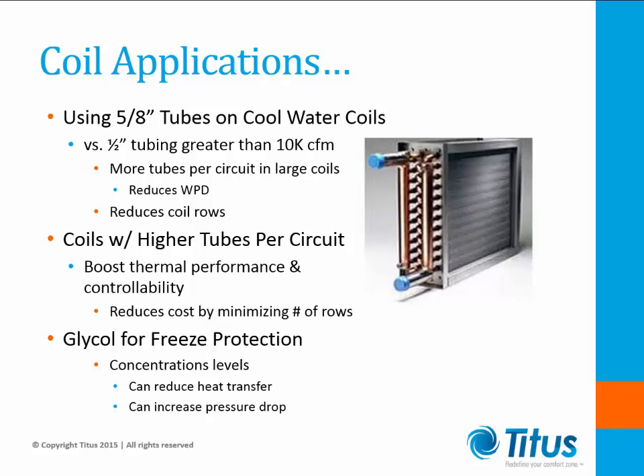Another method of saving space and money within coils is selecting coils with higher tubes per circuit. Pushing the water pressure drop to the limit can boost thermal performance and controllability. This may allow you to select a coil with fewer rows and again cut down on the coil depth and cost. When using glycol for freeze protection, use the lowest concentration possible. Glycol reduces heat transfer and increases pressure drop in coils. This requirement can push vendors to use larger coils.